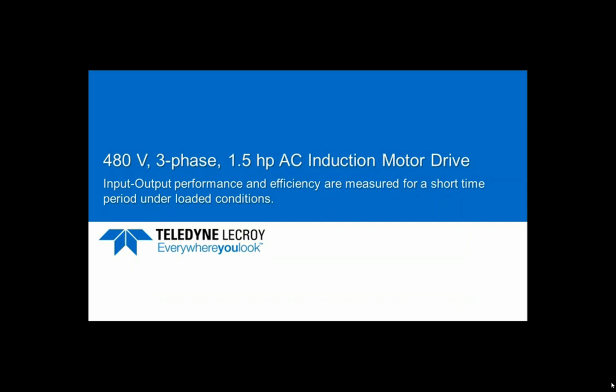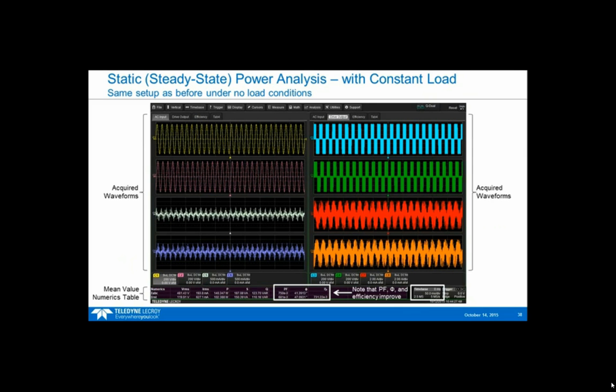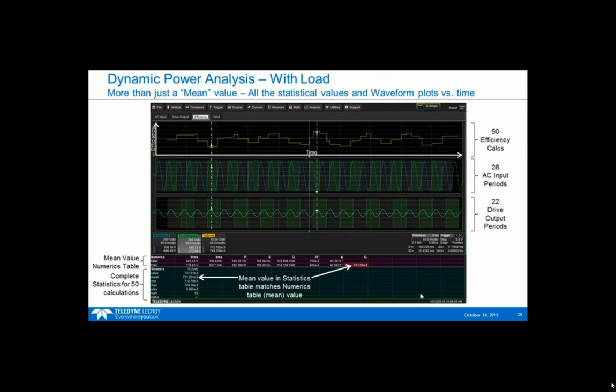Now behaviors over time aren't very interesting when your drive is in a very steady state condition. So let's take a look at a few more conditions. This is that same setup as before, but under load condition. This is the same acquired waveform set with my output waveform set here. You can see that the power factor, phase angle, and efficiency improve, as would be expected under load. We're looking at the same time period as before, and now we're plotting these same waveforms. Again, we have the efficiency over time waveform here, and I get these values again. It's pretty much the same scenario as before.